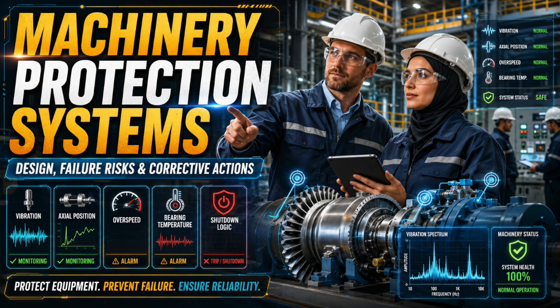A healthy channel should be positively indicated. A faulted channel should not disappear into the background. Maintenance bypass should be controlled and visible. Disarmed shutdown status must be obvious. Never normalize protection impairment. Never let a bypass become permanent. Never treat a faulted protection channel as just an instrument issue without understanding the risk.